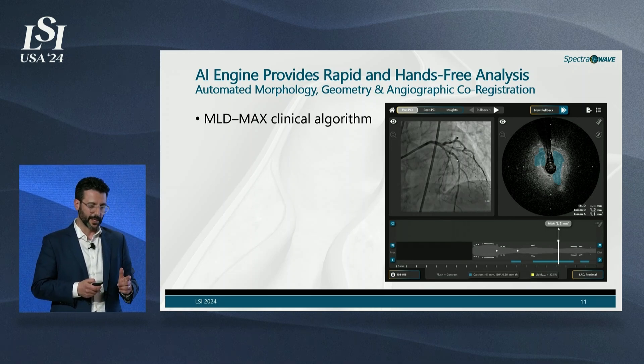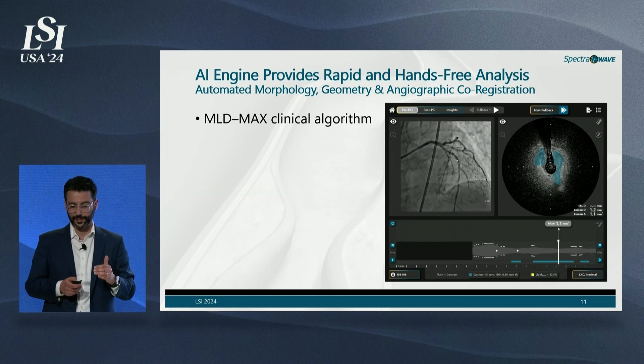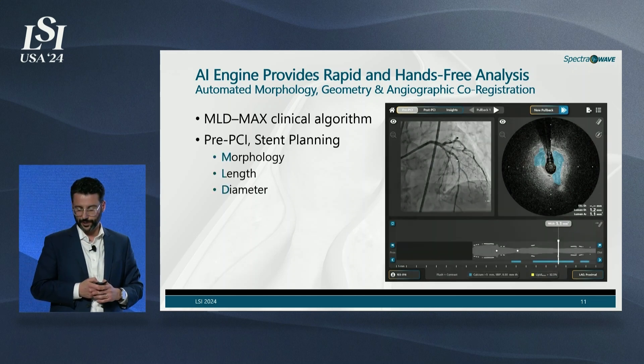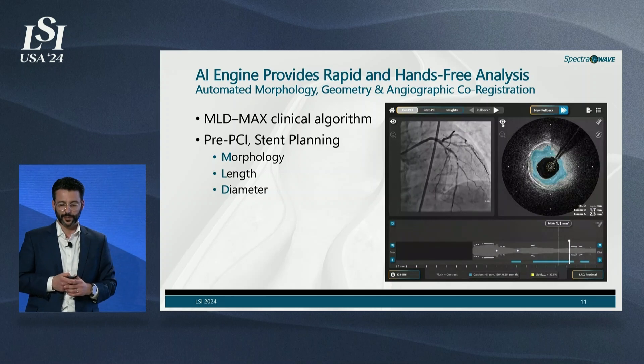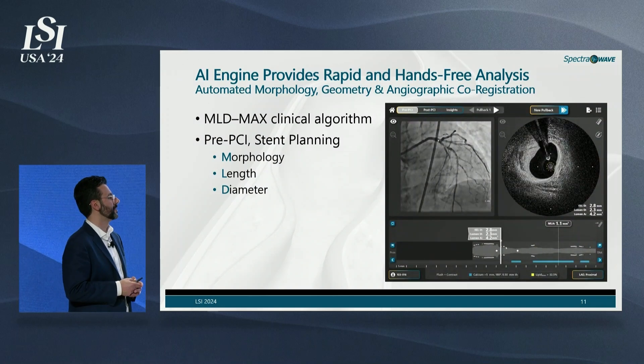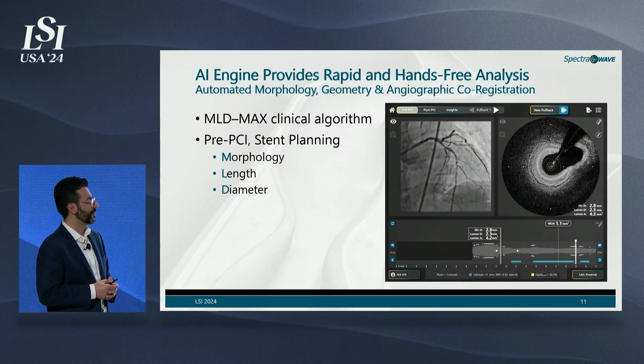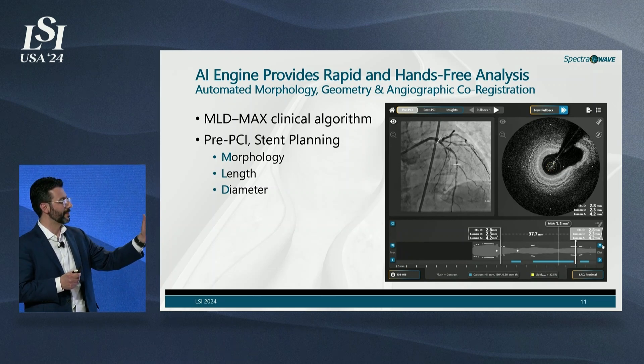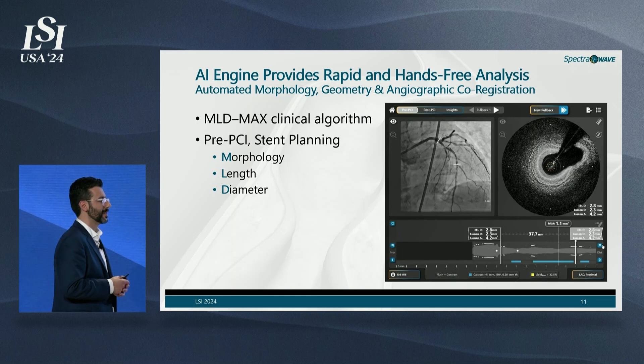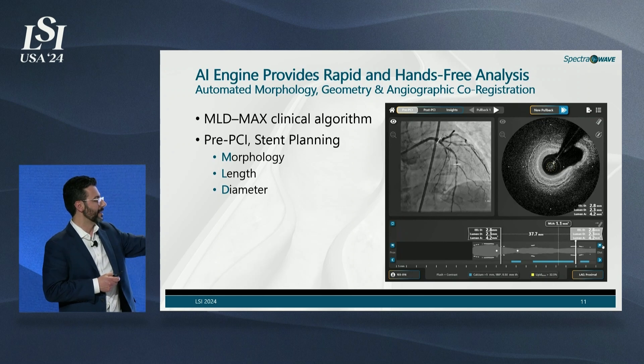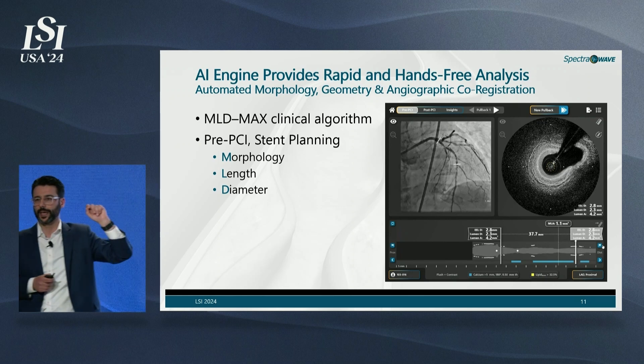Beyond image quality, it's about how quickly the physician can get to the answer. Using the standard MLD max algorithm, our platform performs a sub-second pullback scan to collect data, and within a few seconds presents all key analytics to the physician. The physician scrolls through and places flags at the desired stent edges, and the system immediately outputs all dimensions needed to size the stent — for example, a 38mm stent with proximal and distal expansion of 2.8 millimeters.